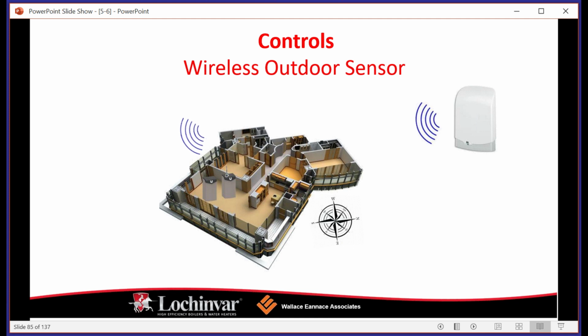So again, the boiler doesn't need to just be dumb and output whatever its outlet temperature is and just do its thing. Based on the outdoor air temperature, it can run at a higher input when it's colder in the morning and then slow down in the afternoon when it gets warm, till we get to a point, typically 70 degrees is where we want to see it, where the boiler says, I don't need to run at all. Okay, so the boiler is going to know when it's warm out and it's not going to run. And again, this is one more piece of the puzzle of how we get that efficiency, is using an outdoor reset.